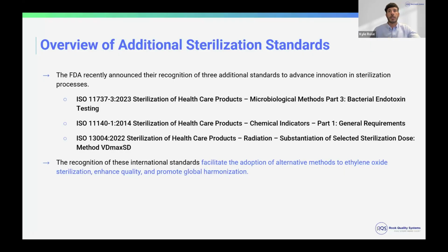Within the scope of these new sterilization standards, the FDA has announced recognition of 3 additional standards recently that are applicable for sterilization processes. So ISO 11737, sterilization of healthcare products within the scope of bacterial endotoxin testing. There's 11140, which covers chemical indicators and the general requirements for those, so the biological or chemical indicators that are used to show that the sterilization cycle was complete. And then also sterilization dose, so ISO 13004, sterilization of healthcare products, specifically on the radiation sterilization methods and how to select the best sterilization dose for your validation. So these are the 3 new standards the FDA has recognized. We'll talk about each one in detail and how you need to update your records to comply with these new consensus standards.